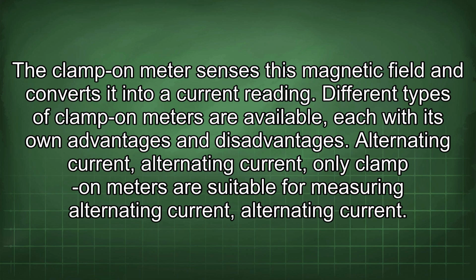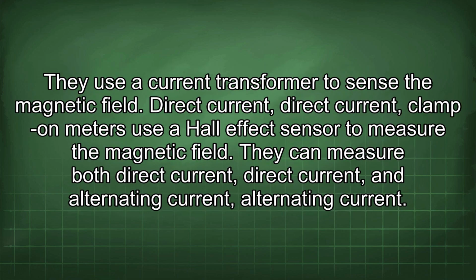Different types of clamp-on meters are available, each with its own advantages and disadvantages. Alternating current only clamp-on meters are suitable for measuring alternating current. They use a current transformer to sense the magnetic field. Direct current clamp-on meters use a Hall effect sensor to measure the magnetic field. They can measure both direct current and alternating current.